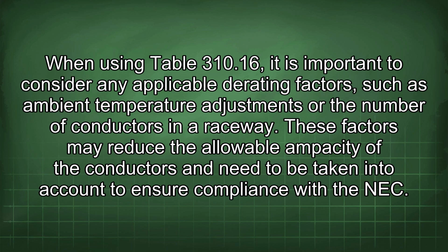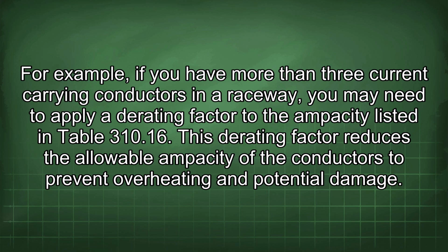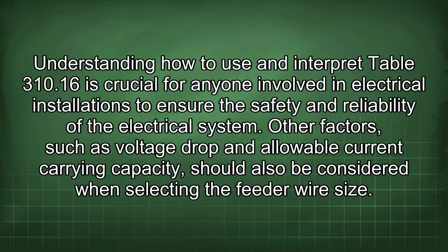These factors may reduce the allowable ampacity of the conductors and need to be taken into account to ensure compliance with the NEC. For example, if you have more than 3 current-carrying conductors in a raceway, you may need to apply a derating factor to the ampacity listed in Table 310.16. This derating factor reduces the allowable ampacity of the conductors to prevent overheating and potential damage. Understanding how to use and interpret Table 310.16 is crucial for anyone involved in electrical installations to ensure the safety and reliability of the electrical system.